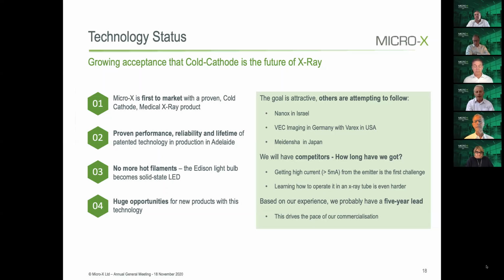Give you an idea, really an entry-level medical device tube needs 100 milliamps. And our new tube that we're developing for the Mark II rover is currently operating at 200 milliamps. So one indication of where the competition is certainly current. Once you've got current from your emitter, you need to know how to operate it in a tube, because it turns out that all the rules that apply to conventional X-ray tubes just don't apply to a tube that's operating in this electronic environment. So based on our experience, we think we've got a five-year lead over the nearest competitor. So the question is, what are we going to do with that in 5 years?